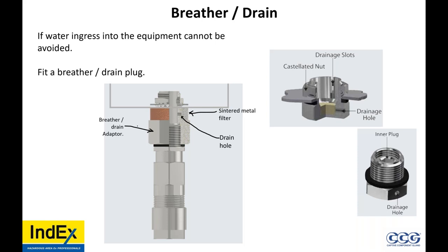This one, CMP came up with the idea of, instead of having to require an extra hole for the breather drain, they worked it into use with a gland. But you still have to put an IP washer between the gland and that accessory. They already have an O-ring built into it at the box as well. Yeah, if you have water entry through the threads here and through the threads here and the threads here, don't you need an IP washer or O-ring at the device side as well?